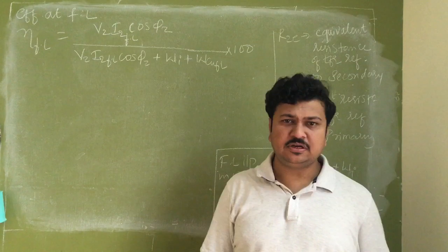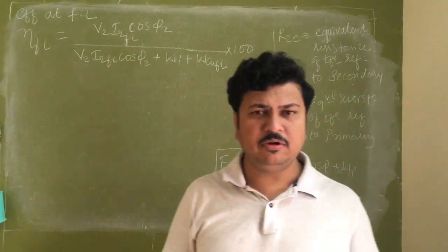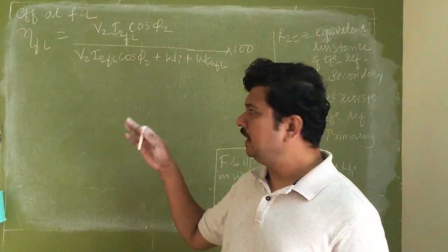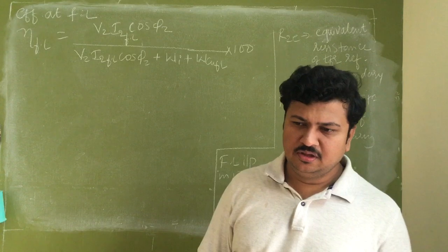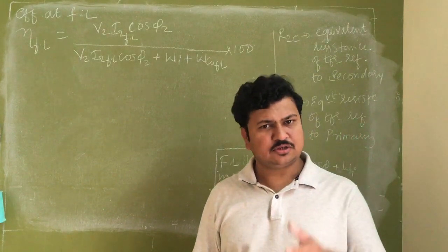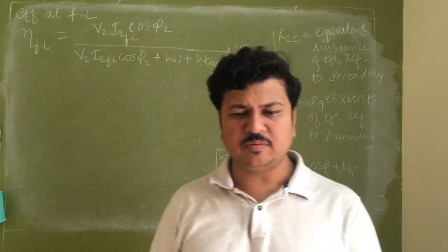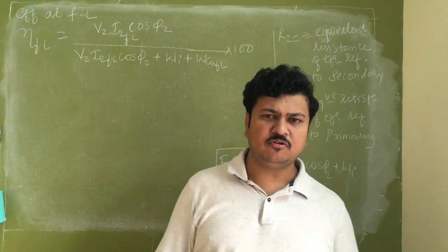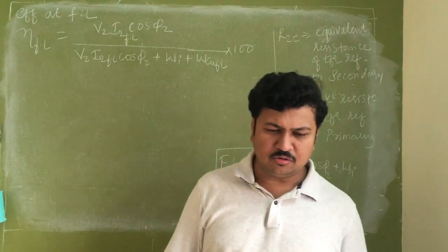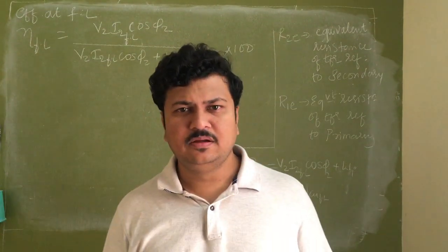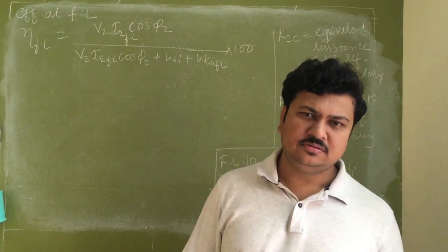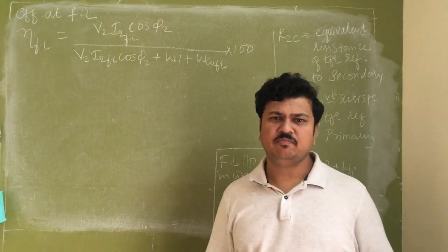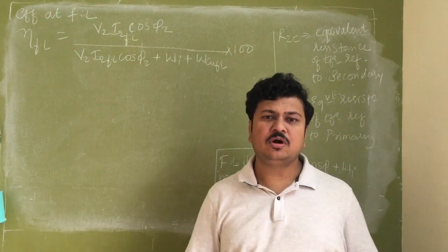Even if I have to service it, the servicing of transformer will not be even once a year. It will be once in 2 to 3 years. So to that extent it has to give the service. Now suppose today the load requirement is 200 kVA and I install a transformer of 200 kVA. Next year I want to increase one more floor of my building, or I want to construct one more new block. There will be additional power requirement. So once that newly constructed load is put into the service, then my transformer will be overloaded.